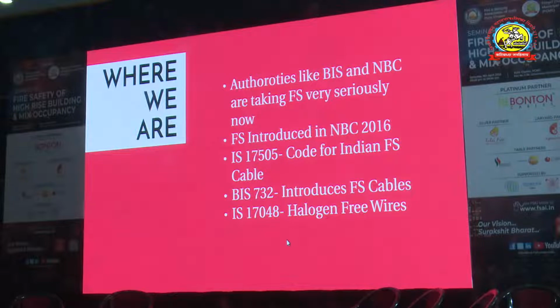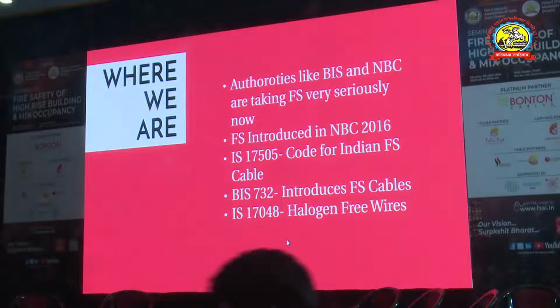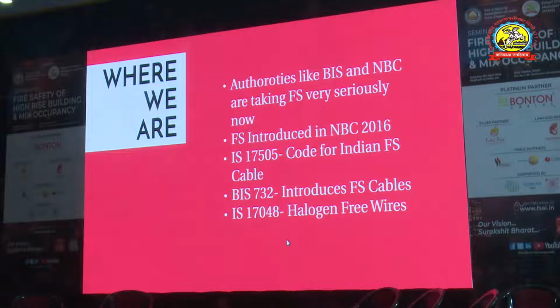As I was discussing, BIS and NBC have taken serious consideration for fire survival cables and included them in their specifications. NBC 2016 covers 8 certain areas like pressurization pumps, magnetic door openers, fire pumps, emergency lighting, and exit signages, all of which must be equipped with fire survival cables. BIS 732 has also introduced fire survival cables, and there's a new code, IS 17505.